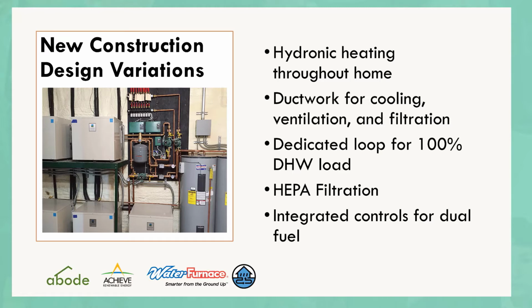Hydronic systems are a little bit more complicated. This is a relatively large hydronic system that has 5 or more heat pumps, and it's providing radiant flooring and domestic hot water, and there's a lot going on here. But even so, it's still a pretty compact install. This number of heat pumps would be a pretty large house, maybe 10, 12,000 square feet.